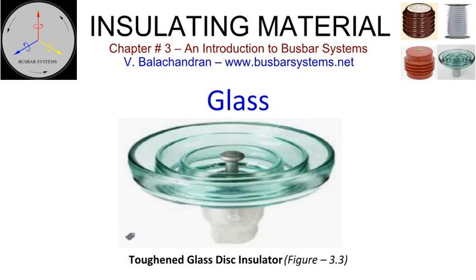One of the advantages of glass insulators is that, unlike porcelain, any component rejected due to defects or shattering while processing can be recycled. It is, therefore, environmentally friendly. One of the major disadvantages of glass insulators is that moisture can easily condense on the surface. This can facilitate the deposition of dust, leading to increased leakage current. Glass insulators can be coated to improve their surface properties. Glass insulators are cheaper than porcelain insulators.